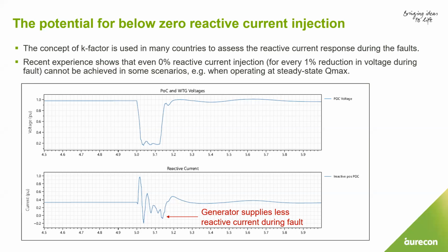The first thing, like I said, is that when a fault happens, what is the overarching objective? What is expected from an IBR or even a synchronous generator? If a fault happens, the voltage goes low, so how can you aid the recovery of network voltages? During the fault the voltage is depressed, so you have no opportunity to raise it up; that's primarily driven by RLC impedances. Just before the fault clears and at fault clearance, if an IBR can inject some level of reactive current, that can assist the faster recovery of network voltages, especially as synchronous generators are being rapidly withdrawn from the power system.